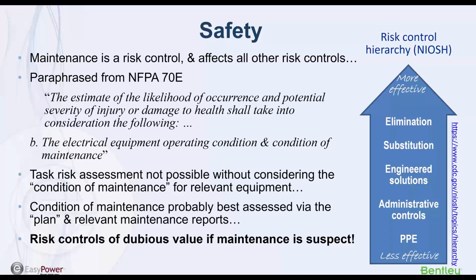When you look at safety, you have to understand that proper maintenance is in fact a risk control, and part of many other risk controls. When you do a risk analysis for a task or operation where people may be exposed to a hazard, you need to estimate the likelihood of occurrence and potential severity of injury or damage to health, paraphrasing 70E. The likelihood of occurrence and potential severity of injury is dependent on the condition of the equipment creating or hosting the hazard. Hence, it further states that the electrical equipment operating condition and condition of maintenance need to be taken into account in that task risk assessment.